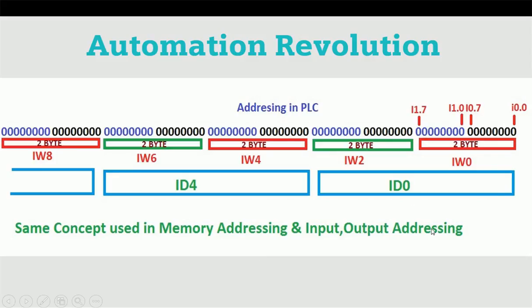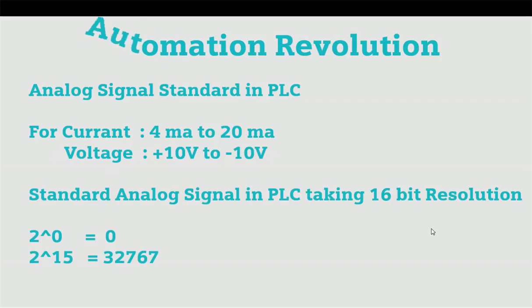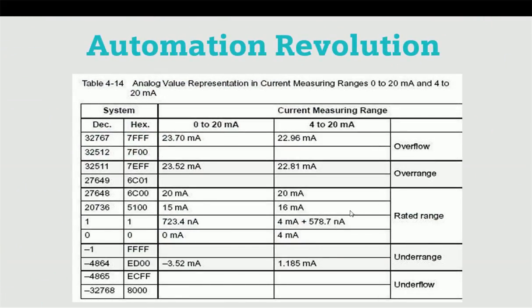Analog signal has two types of standard: current and voltage form. In current form, analog signal is taking 16-bit resolution. If we convert this binary into decimal, the total range would be 32,767. Here we can see one graph showing the standard rated range. If we go above 20 milliampere or 22 milliampere, this value will come in overflow or over-range. PLC will not consider this over-range or overflow range limit. That is why we will see only 4 milliampere to 20 milliampere as the rated range, so we will consider 0 to 27,648 value.